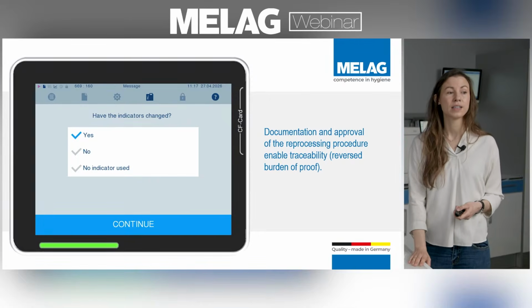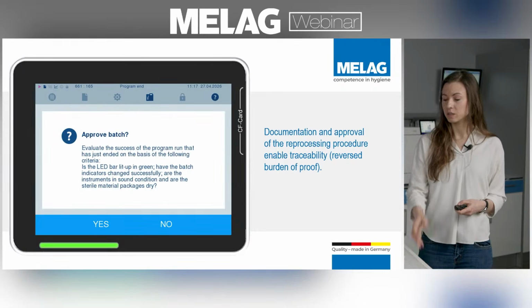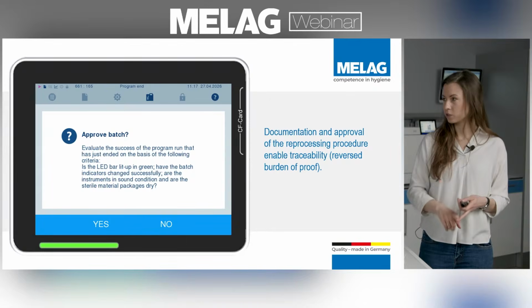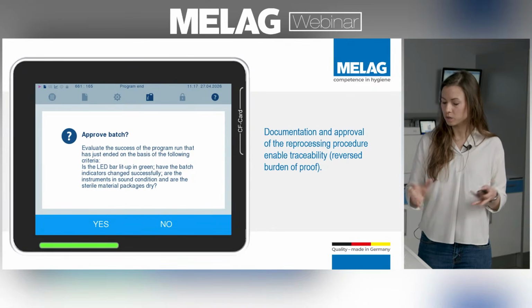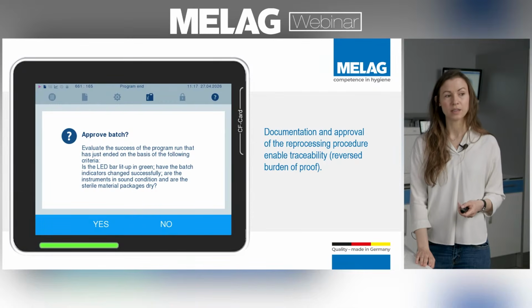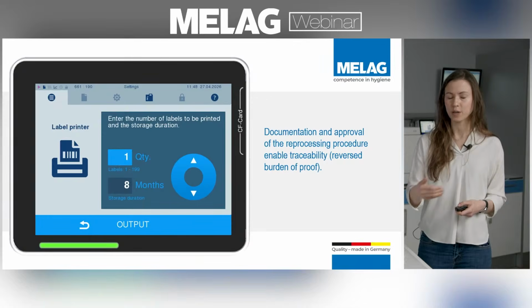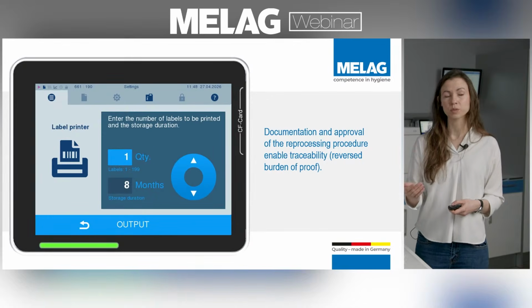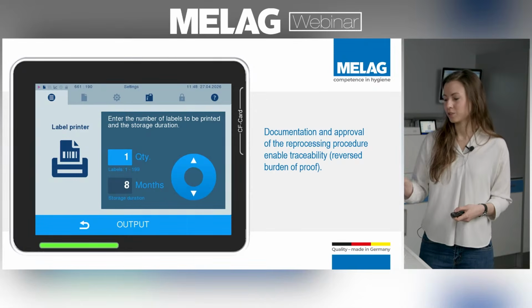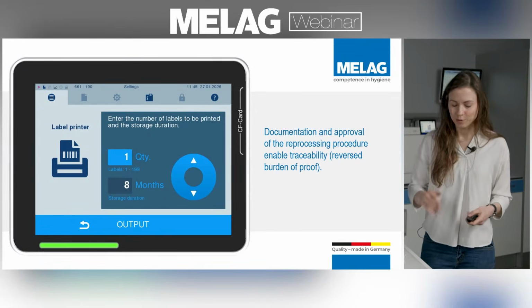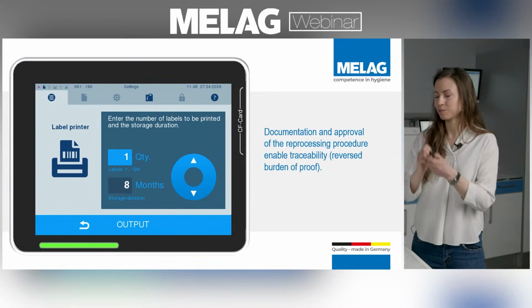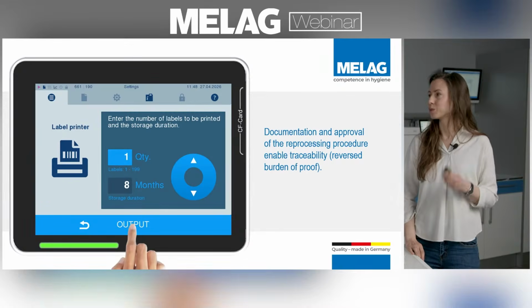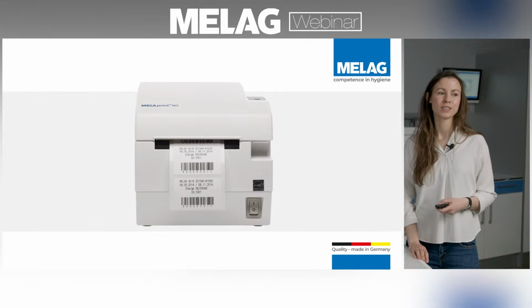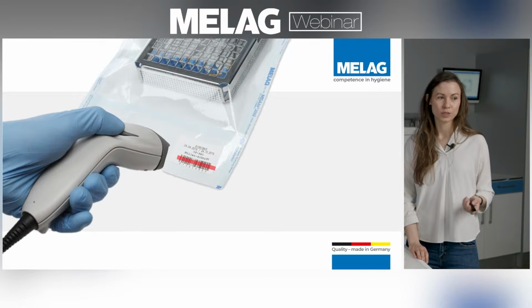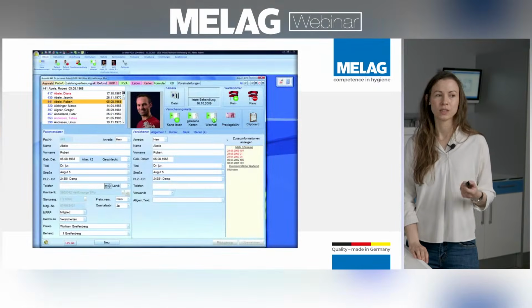Like the helix test. And you continue, and then you say, do the instruments look good? Is the packaging all right? Is everything dry enough? Do you think this batch can be released, or this instrument? And then after you say, yes, it looks good, I want to release it, you can set the number of how many labels you want to print out. That means, for example, if you have maybe 15 instruments in your sterilizer and one package just popped open, then you can say, I only want to print out 14 labels. You print them out, stick them onto your instrument packaging, and afterwards, when you use the instrument, you scan the code and document it in the patient file.